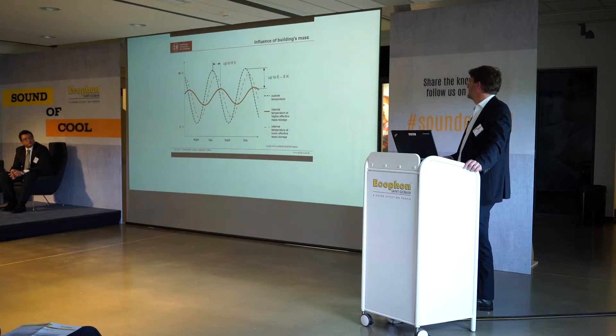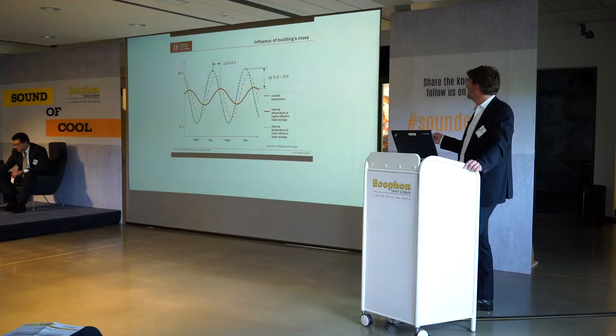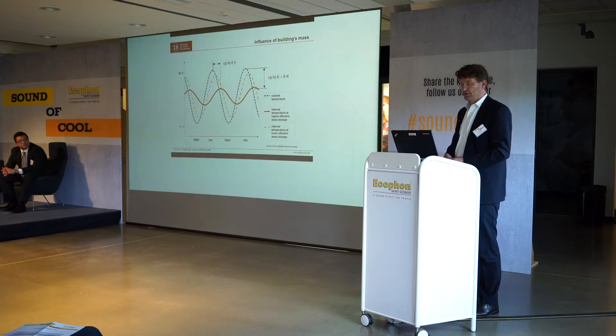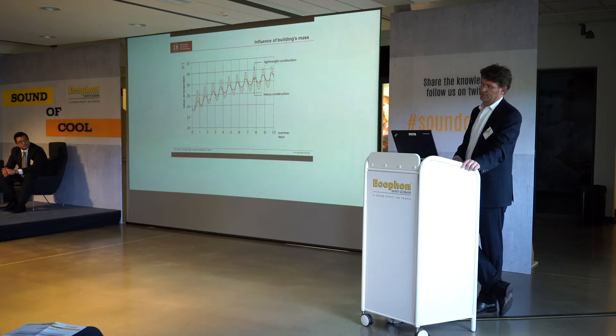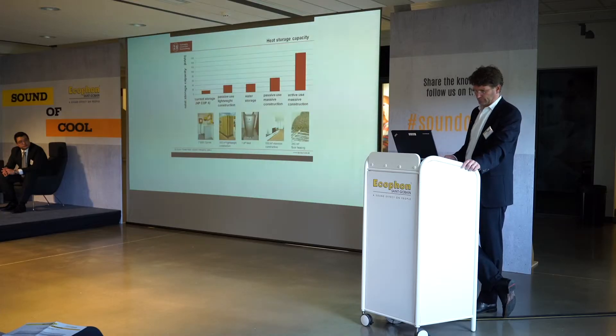The blue line is the outdoor temperature. If it is possible to include a concept with thermal mass and heavy construction, you can achieve a higher difference between the outdoor and indoor temperature. This is particularly useful for night cooling — when there is a large temperature difference, we can cool down during the night, achieving a more comfortable climate during the day. Over a longer period, heavy construction also shows lesser variation between day and night temperatures compared to light construction.